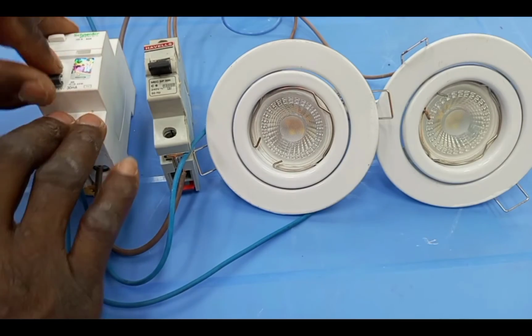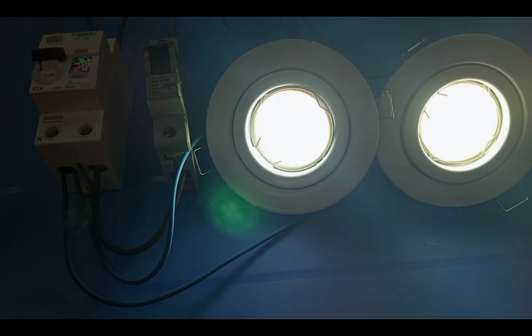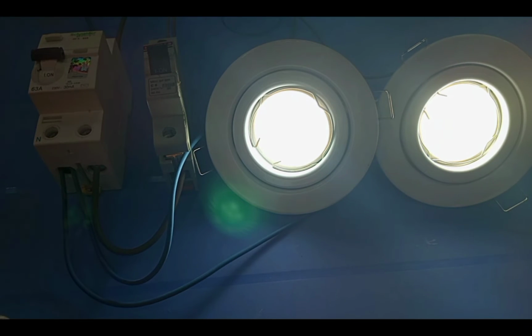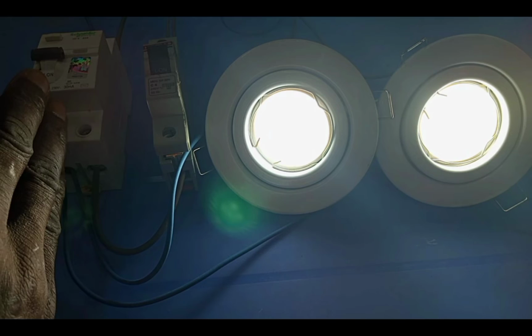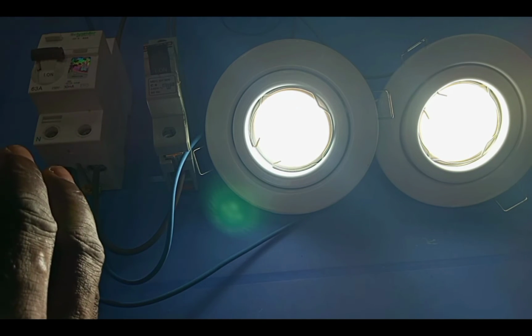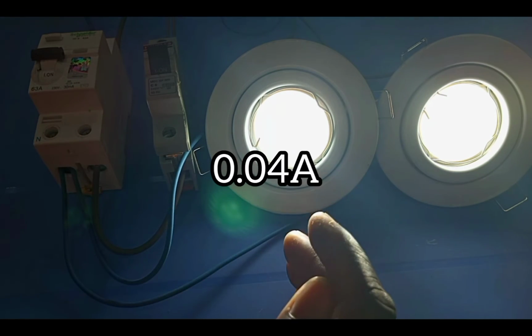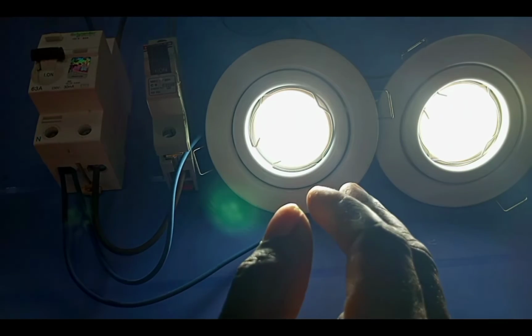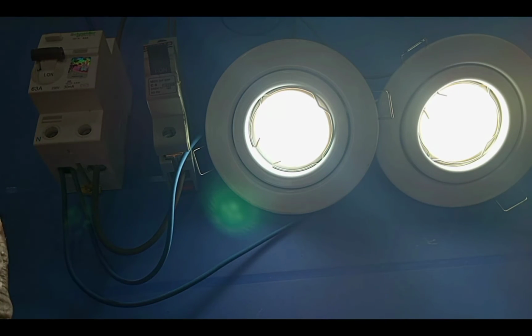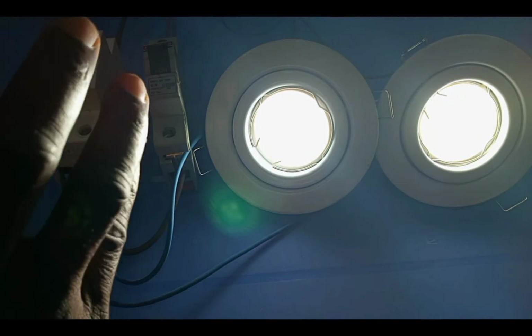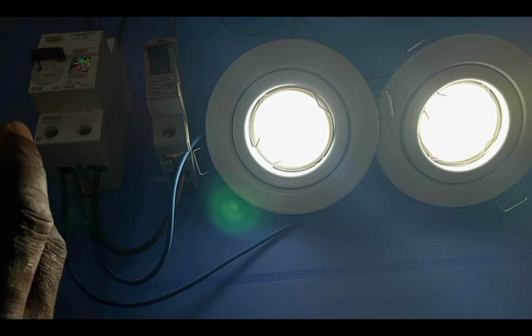Okay, so if this goes on and this goes on, both lamps work correctly, because though I have added another load, what will happen now is that the RCD will monitor that 0.04 amps will flow through the live and then back through the neutral. So far as that condition is met, the whole system will work. The RCD will stay on without operating.